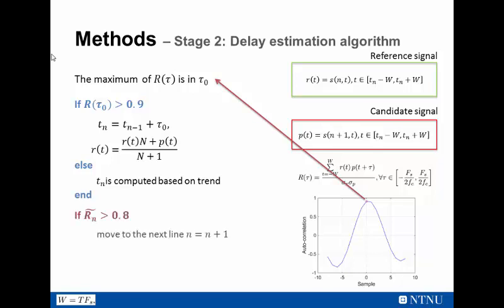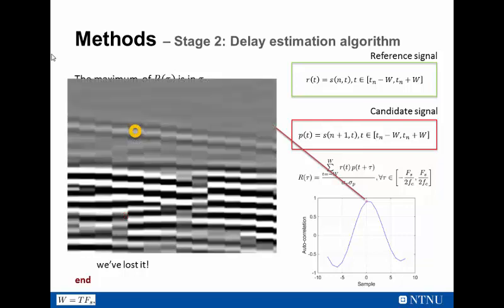Otherwise, I can calculate the delay as a trend based on previous values. I also keep a running average of the maximum correlation values for each RF scanline. So if that value is greater than 0.8, I can move to the next scanline. Otherwise, I'll stop because I consider that I have lost the pulse. So well, this will work in theory, but in order to do that, I really need a good seed. A seed that is sitting precisely on top of the lumen-intima pulse. But that is quite difficult to get.